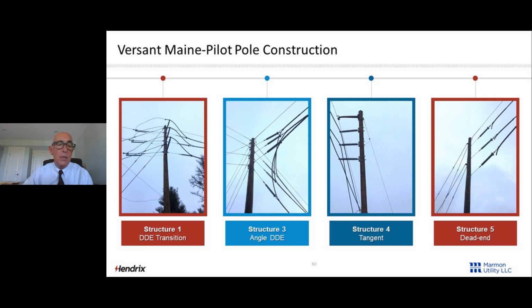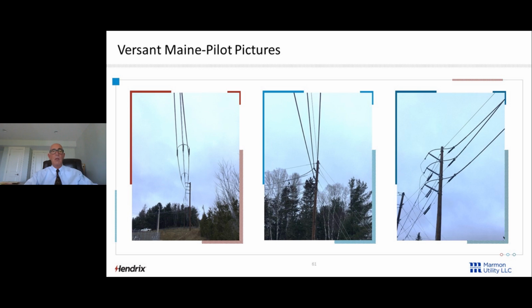There's some photos, double dead end transition. If you look closely, you'll see the arresters there, since you always need a surge arrester at the intersection of a covered to bare transition, the same as you would put arresters on your riser poles. You see a double dead end. We've got a tangent, and then a final dead end, and that was a vertical dead end. We decided to build it that way. A couple more photos, I guess. That's the profile on the left.